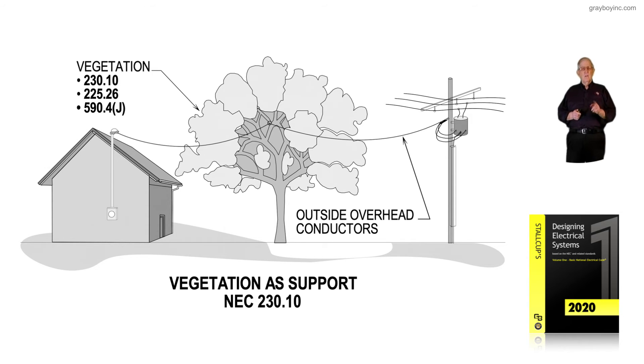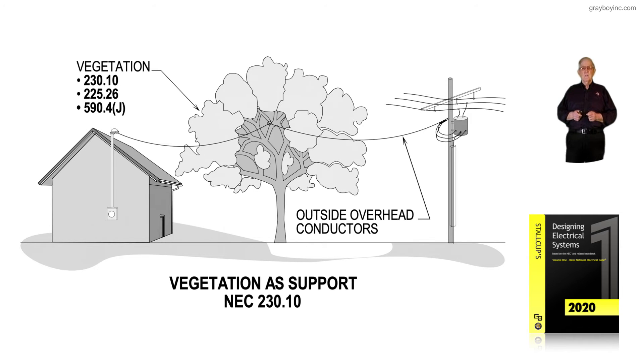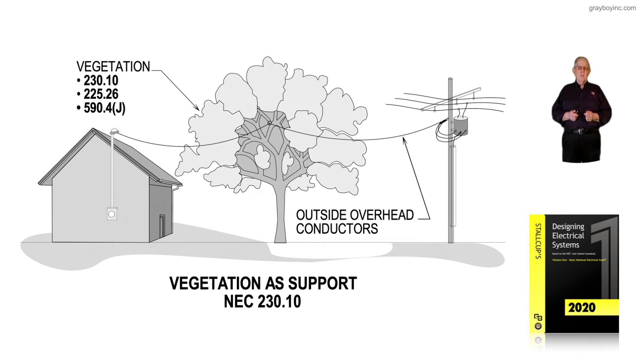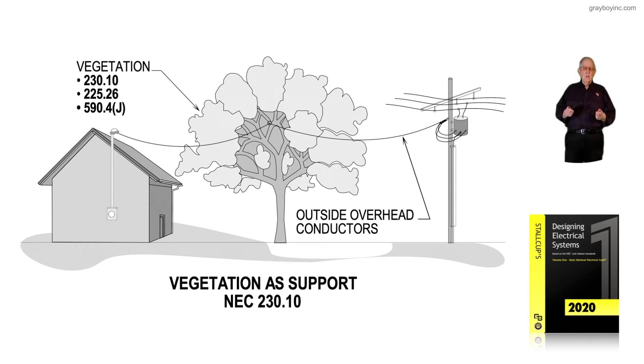Inspectors would say, no, it would be the same for a dead tree too. And contractors said, well, no, it's not what the code says — it says live vegetation. Can't you read your own code? This started disagreements between installers, contractors, designers, and so forth.